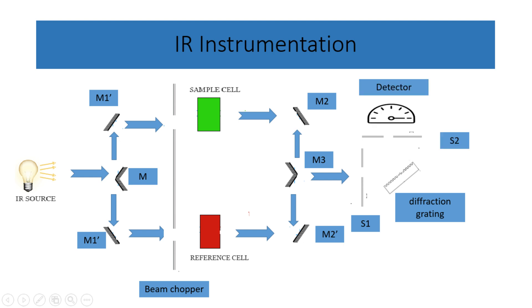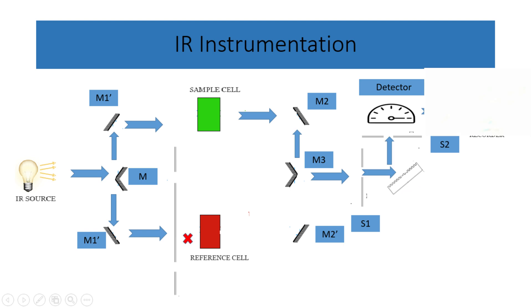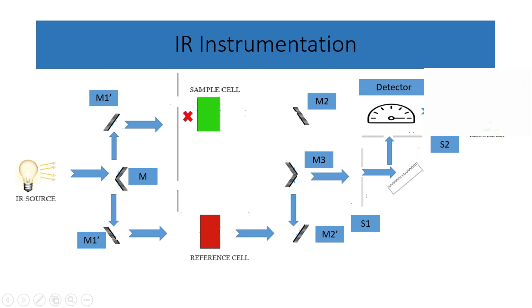Afterward, the beam chopper directs the sample radiation toward the detector while the reference radiation is blocked. The sample radiation goes through the same steps as the reference radiation and reaches the detector. This alternating process continues throughout the analysis.